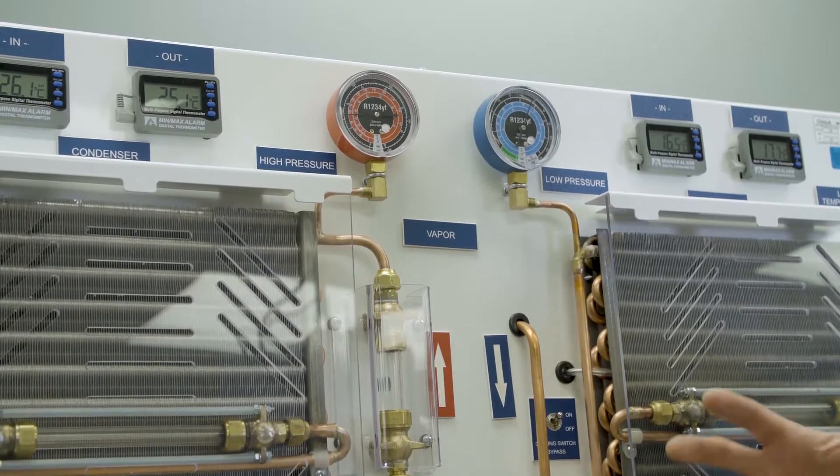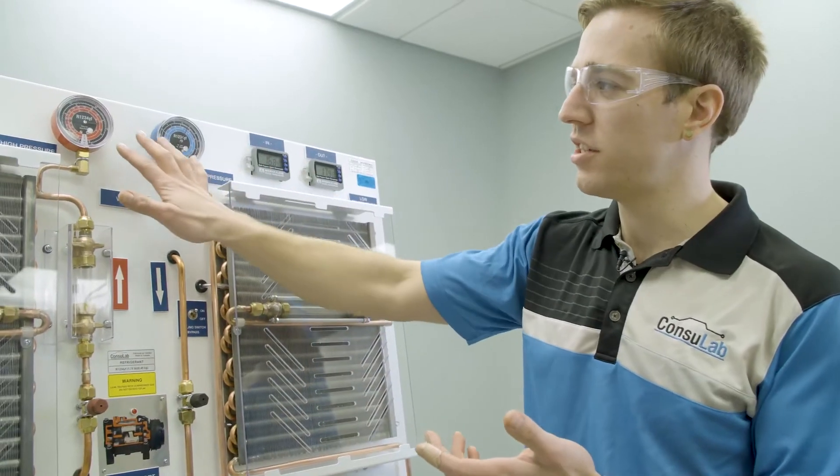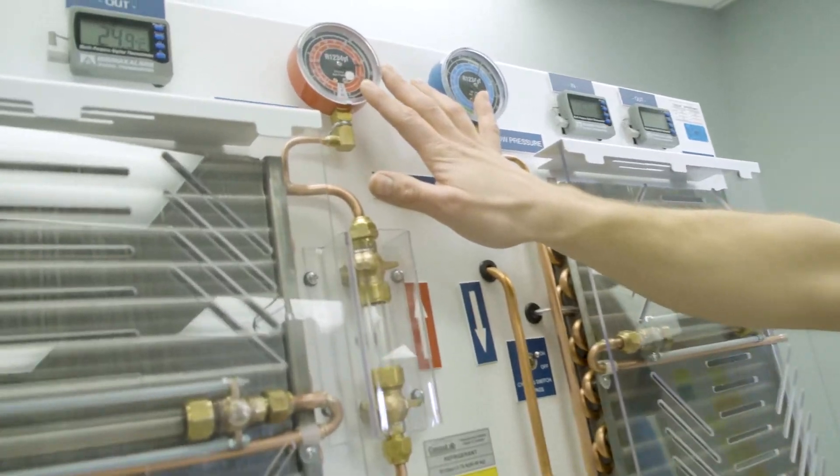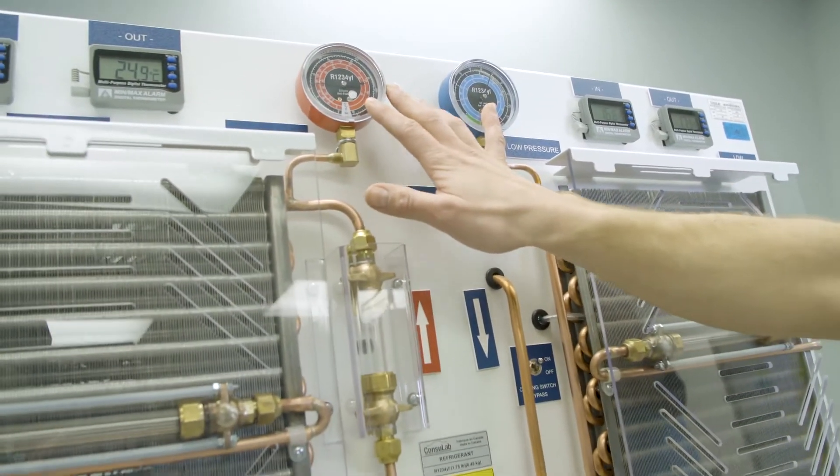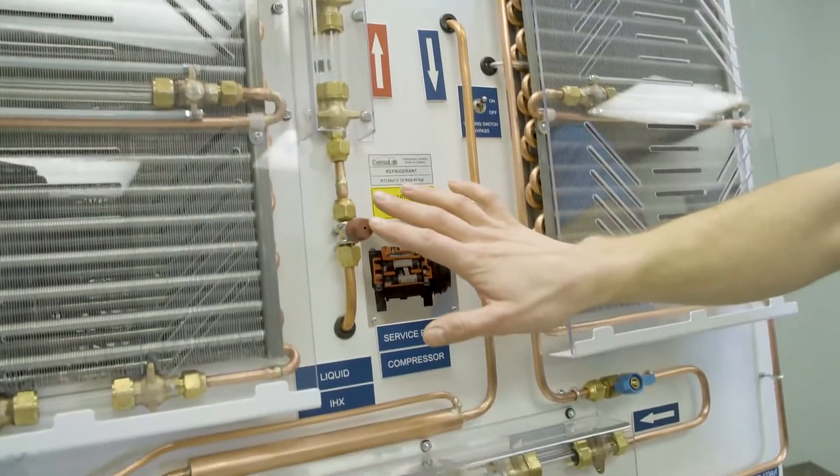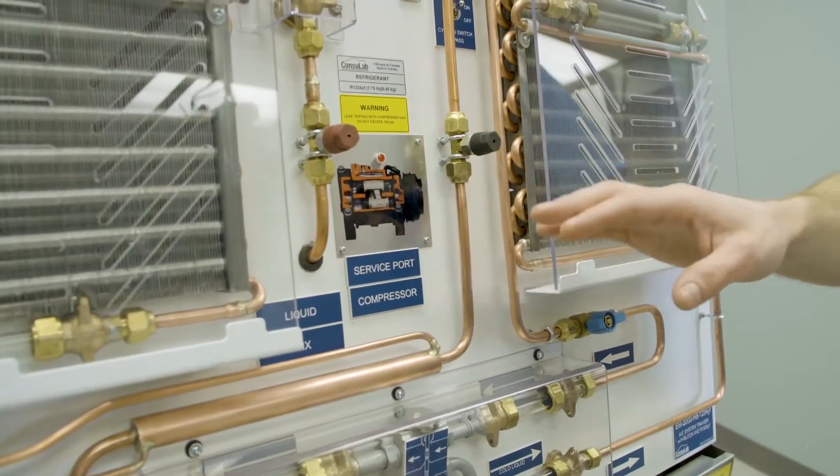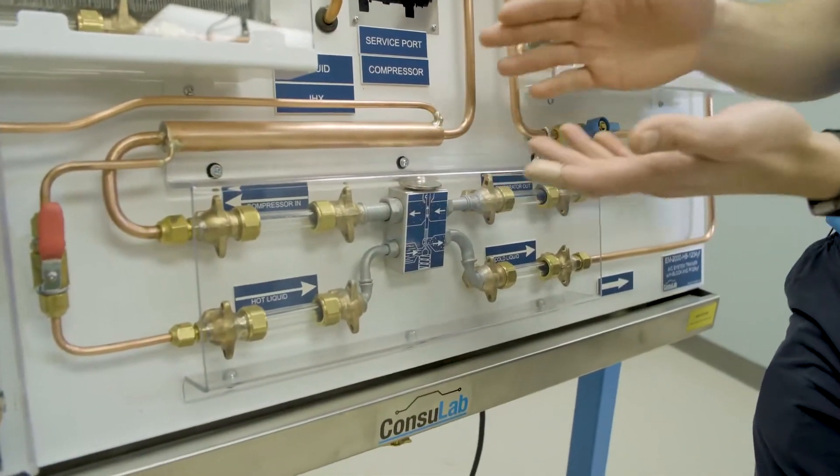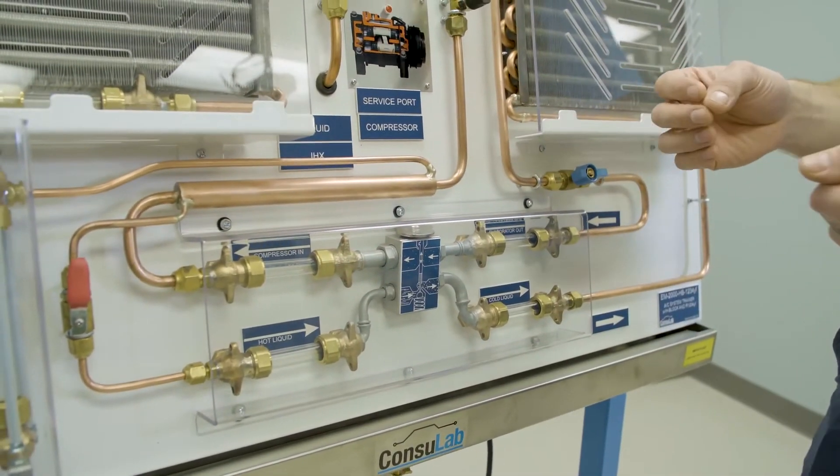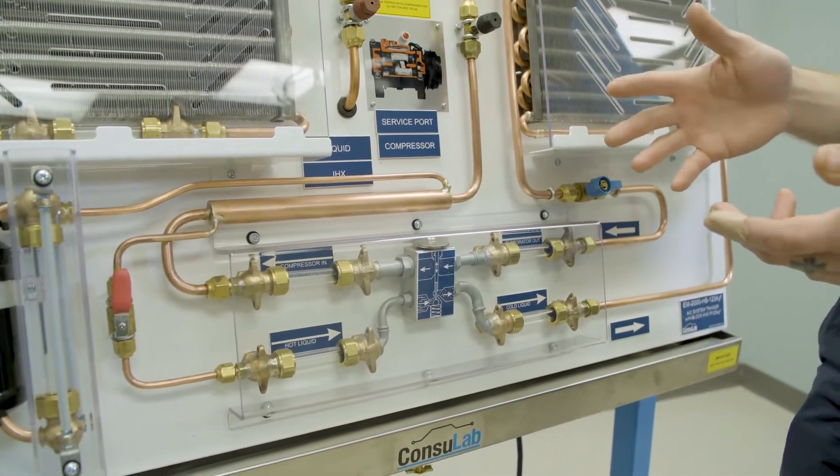Now some of the changes that we have with this new product. We've had to change the gauges, so these are new gauges for our 1234YF refrigerant. Following that we've had to change the service ports here and we've added another component. Now this is called the IHX, this is an internal heat exchanger and it increases the overall system efficiency.